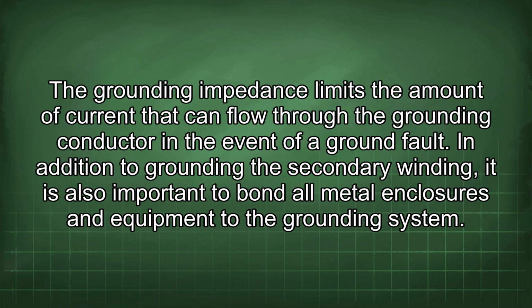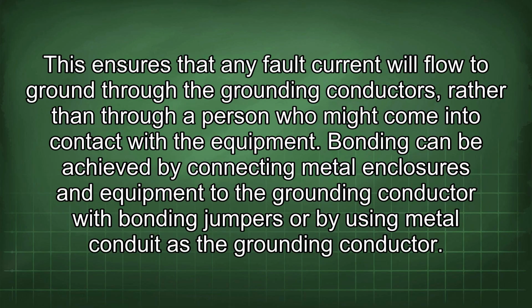The grounding impedance limits the amount of current that can flow through the grounding conductor in the event of a ground fault. In addition to grounding the secondary winding, it is also important to bond all metal enclosures and equipment to the grounding system. This ensures that any fault current will flow to ground through the grounding conductors rather than through a person who might come into contact with the equipment.